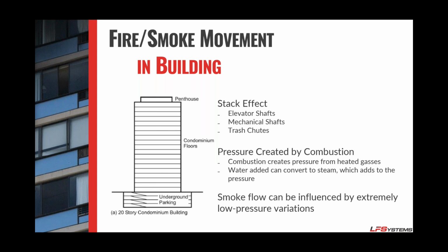Now, there are many things that affect the flow of smoke in the event of a fire. Primarily, stack effect is a huge one, where smoke can travel up elevator shafts, mechanical chutes, and trash chutes. In addition, there is a pressure created by the fire itself. When something catches on fire, there's a pressure wave behind it. And if there's a sprinkler system, that water hits the fire and flashes to steam, which adds even more pressure.